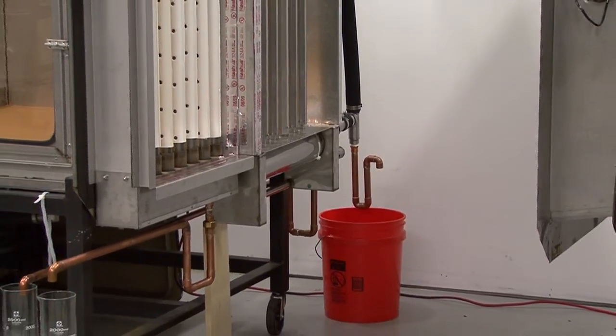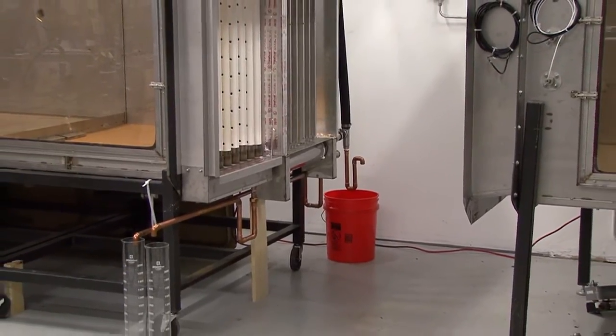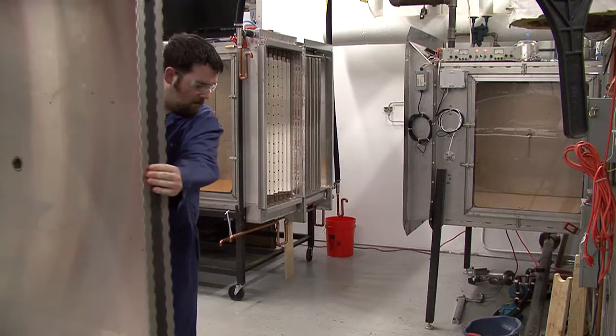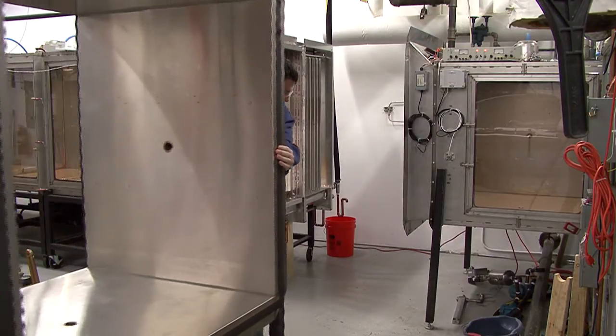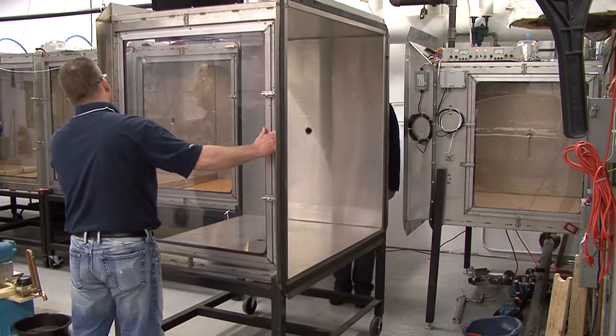To ensure accuracy, we are simultaneously testing two dispersion tube assemblies with the same number of active dispersion tubes in the same dry steam glass wall testing duct. The duct has a 53 degree Fahrenheit horizontal airflow of 1,000 feet per minute.